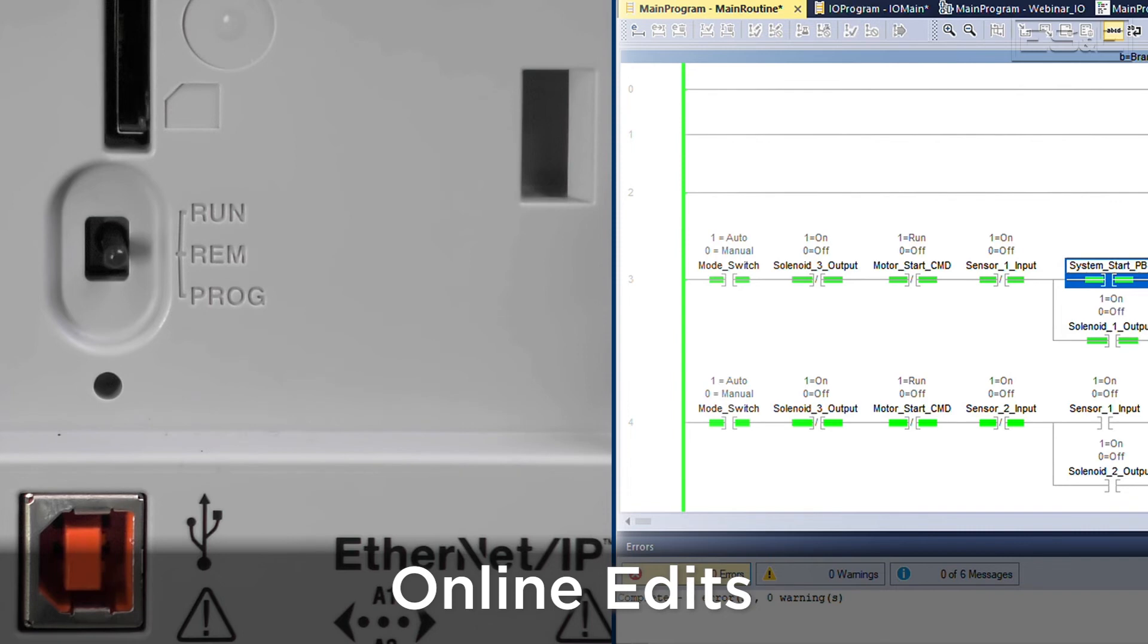You can see the green power flow of your code, then make a modification, compile, and test those edits to verify that they worked as anticipated, then store them into the controller. If they do not work, you can cancel the edits, which will revert back to previously executing code.